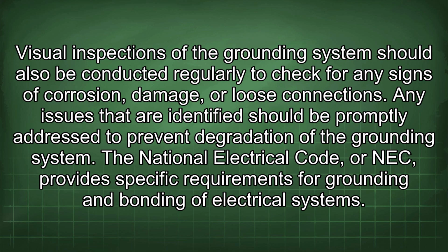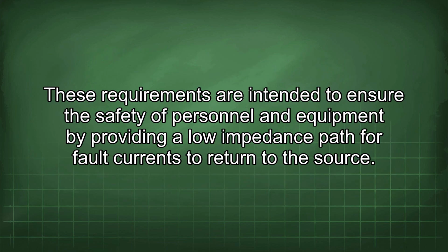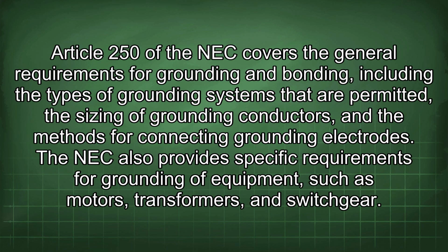The National Electrical Code, or NEC, provides specific requirements for grounding and bonding of electrical systems. These requirements are intended to ensure the safety of personnel and equipment by providing a low impedance path for fault currents to return to the source. Article 250 of the NEC covers the general requirements for grounding and bonding, including the types of grounding systems that are permitted, the sizing of grounding conductors, and the methods for connecting grounding electrodes.